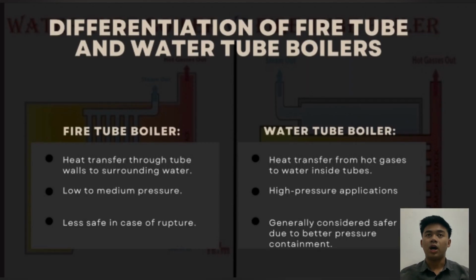Yeah, so today I want to present the differentiation between fire tube boiler and water tube boiler. So the first differentiation is heat transfer. In a fire tube boiler, heat is transferred through the wall of the tube to the water surrounding them. In a water tube boiler, heat is transferred from the hot gas to the water inside the tube. So the next differentiation is pressure. Fire tube boilers are typically used for low to medium pressure applications. Water tube boilers suit high pressure applications such as power generation.